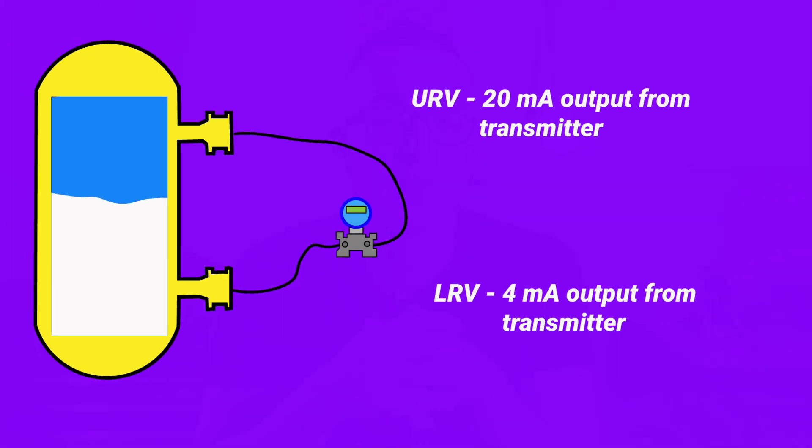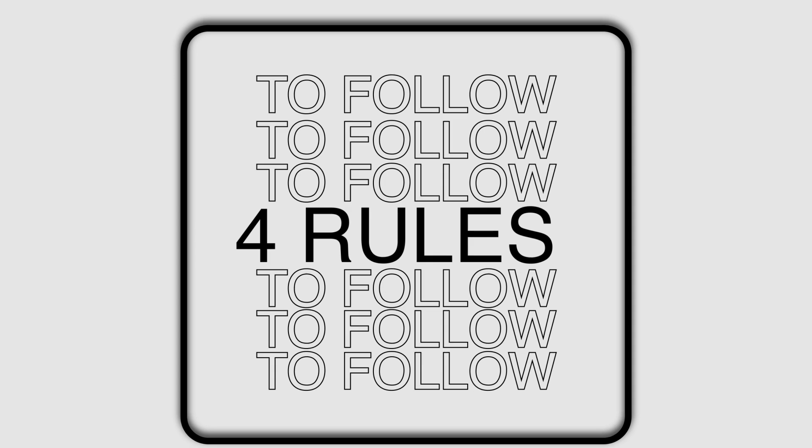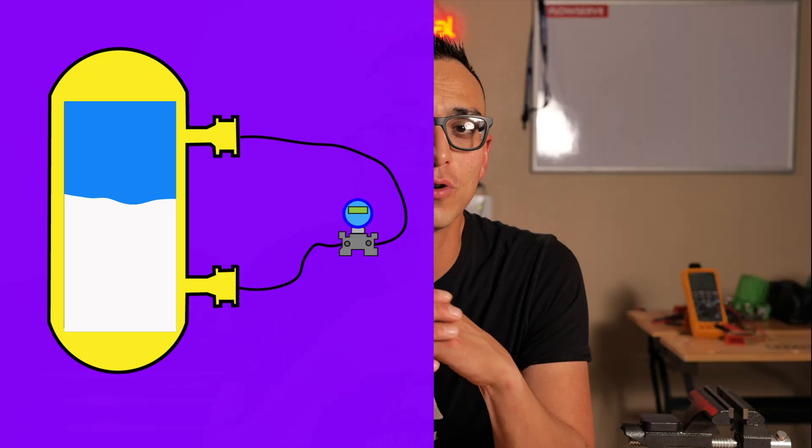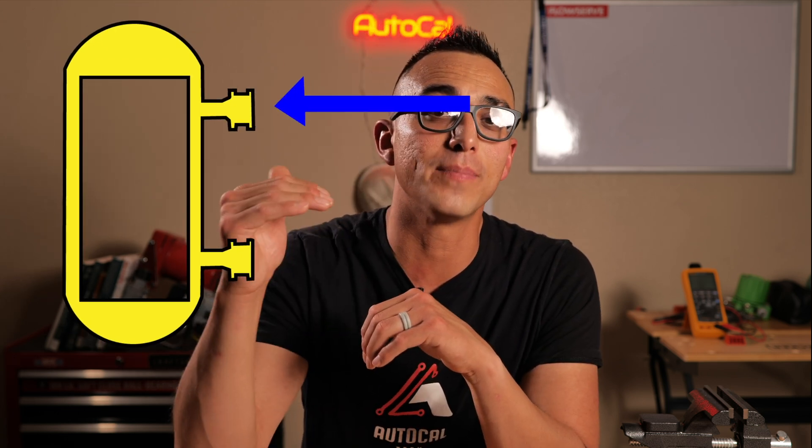However in order for the interface level transmitter to work correctly we got to make sure we follow a few rules to be able to set this up. Rule number one, since this type of level transmitter uses differential pressure to calculate its interface level, the level must always be above the low side or the top tap.